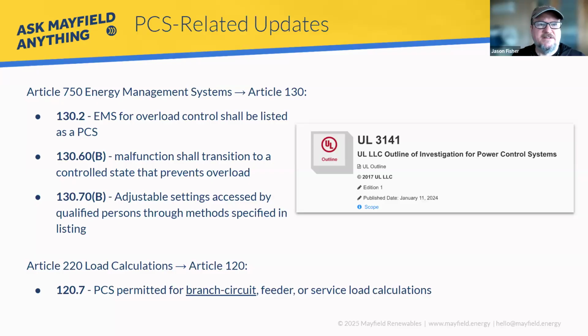I think one of the reasons we have it here for ESS is, ever since we started AC coupling - back when we got started, everything was DC coupled. But once we started AC coupling PV and storage, the obvious question was: I have to call both of these a source and add up both of these things. But when my PV is producing, I'm also charging the battery, and so on. The fact is that the NEC just said no, those are two sources, and there wasn't anything preventing the two of them from both exporting at the same time. So you had to add those two nameplates together.